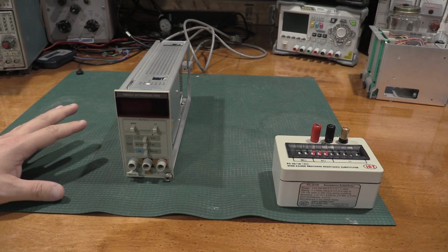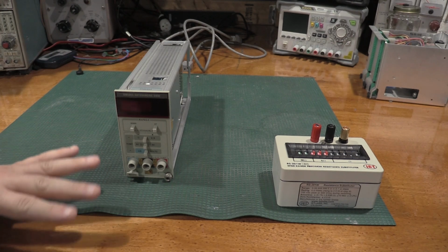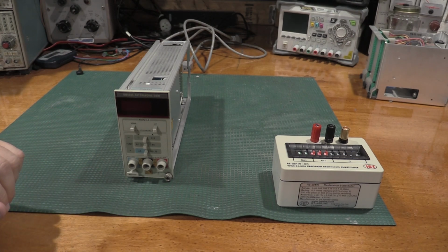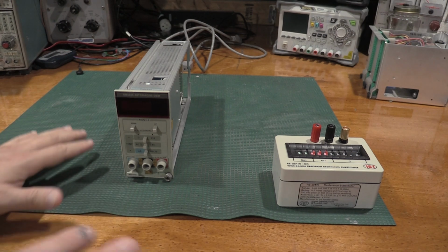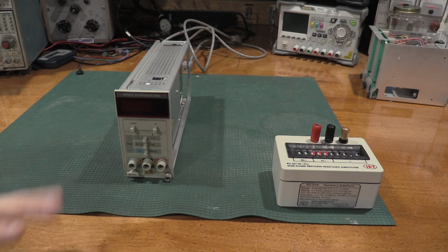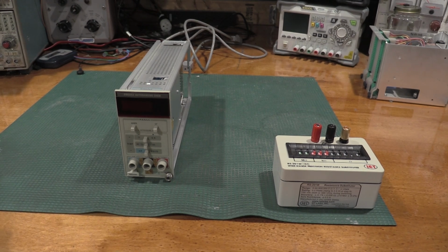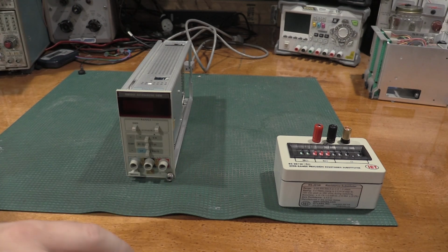This is also when we shifted focus from alignments to calibrations. Those 2 terms are thrown around quite a bit, and there's actually a very distinct difference between them. If you don't understand that, you might send something out for calibration and be surprised when it comes back no better than you sent it out. I did a video on this about the 7510 coming back from calibration. I actually need to send it out again just to get it checked. I don't expect there to be any problems with it.